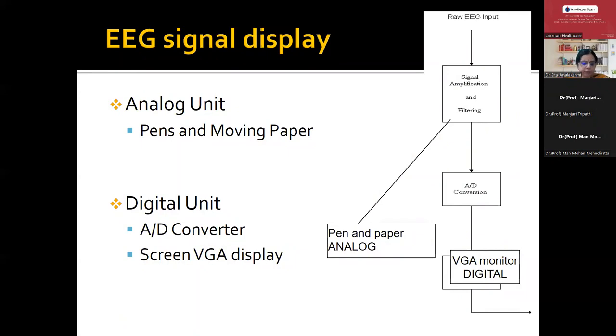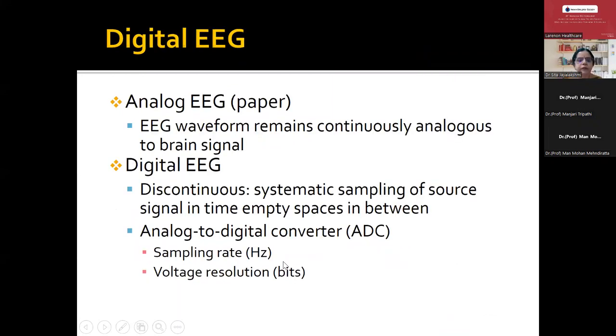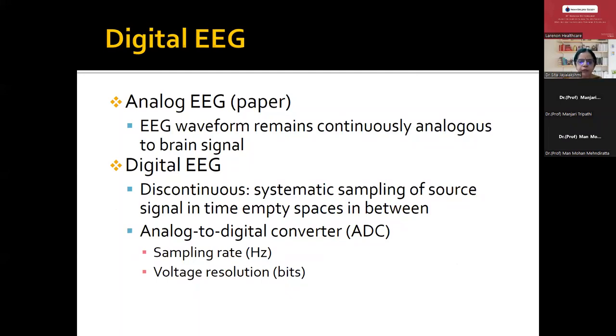So once we know the amplifier with its high frequency filter, low frequency filter, and notch filter — then how is the display generated? We now understand how we place the electrodes on the surface, how they come to the junction box, then to the amplifier, and after that how it is displayed on the monitor. In analog units, it was always pen and paper, but nowadays we don't have that. Coming to the digital unit — normally the recording comes as alpha, beta, and delta waves. The digital unit has something called the A-to-D converter, and in addition there is a digital display.